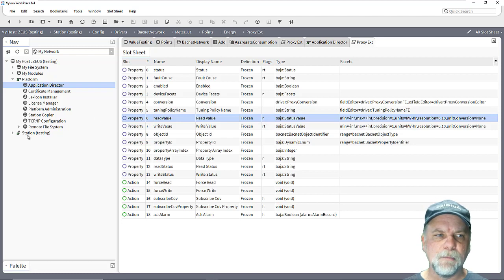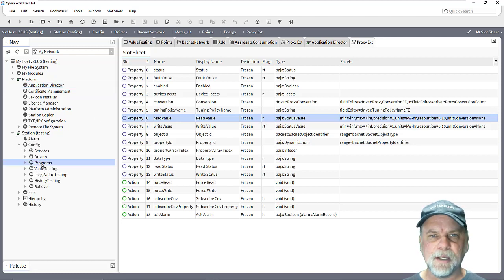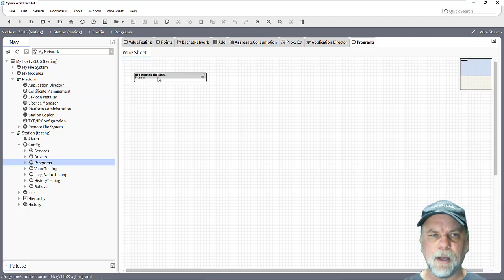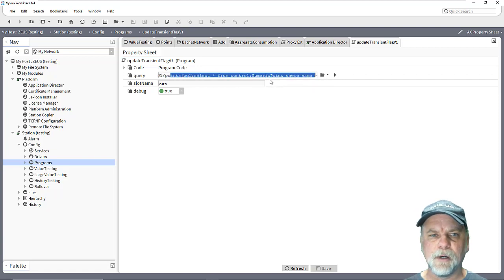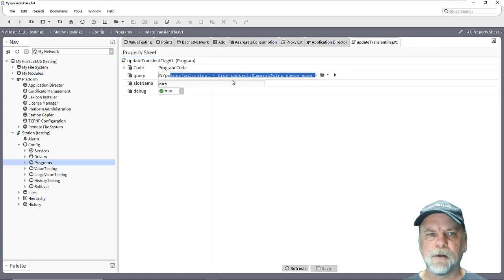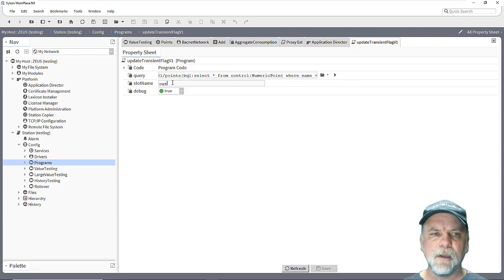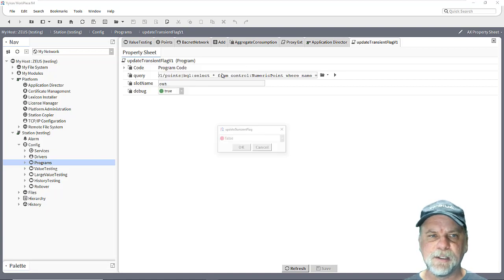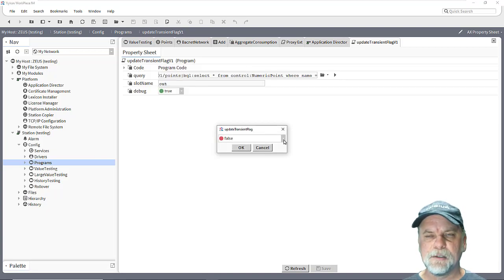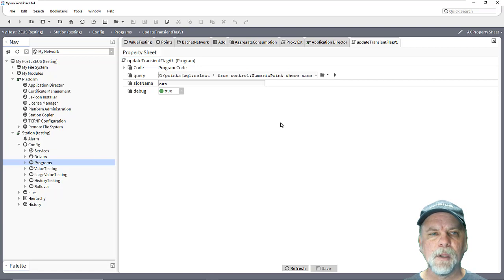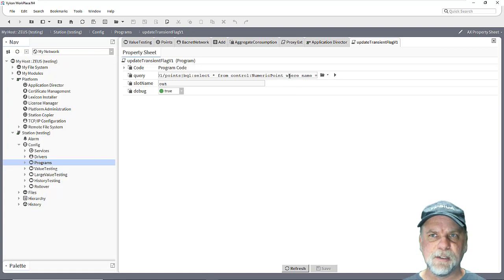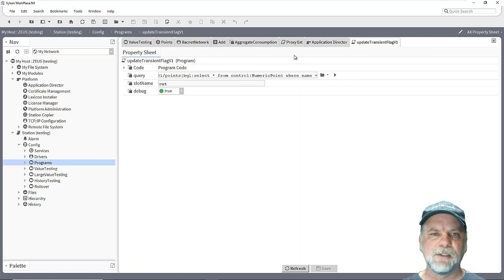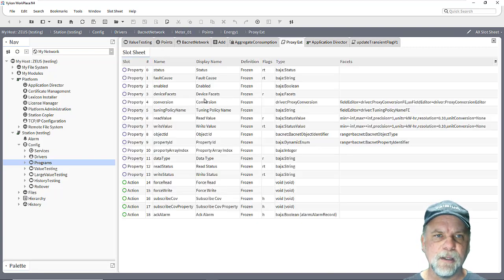So to do that there's probably a number of ways that you go about doing it, but in my case I have a program object here and this program object is designed to submit a BQL query for numeric points in the name that you know meet a certain criteria, and there's a slot name here. So there's an action on this program object to update the transient flag, and if I submit a boolean false then that says remove the flag. If I submit a true then that says to set the flag, to add the flag. So just running that program object I can go through and for those particular points which are persistent in those devices where I don't want to initialize a default value on station restart, then we can clear that transient flag.